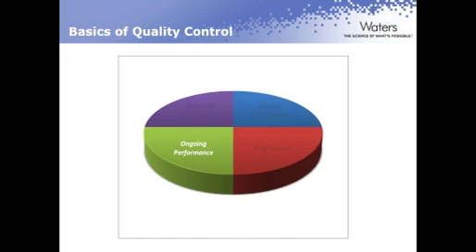Analysts. Okay? Each analyst on your staff is going to do things slightly different, so they are a variable. The instruments are a variable. The conditions change sometimes on a daily basis, sometimes during the day. Certain instruments are susceptible to changes in not only temperature, but also in changes in the humidity in the lab. Okay? Another variable could be standards and reagents, either made up in the laboratory or purchased. So generally, you hope that you're buying standards from a competent provider so that differences in standards will be minimal. CRMs are good to purchase because the variability in standards from lot to lot from a CRM provider is minimal. Okay, but also reagents that are made and purchased can provide variability.